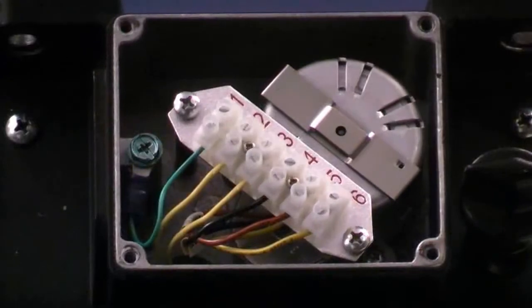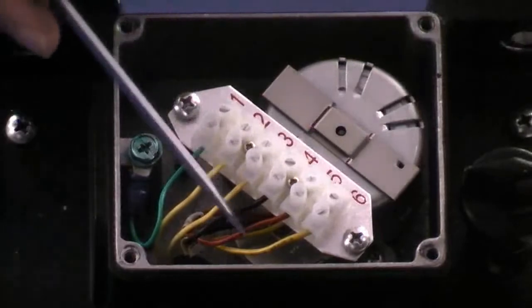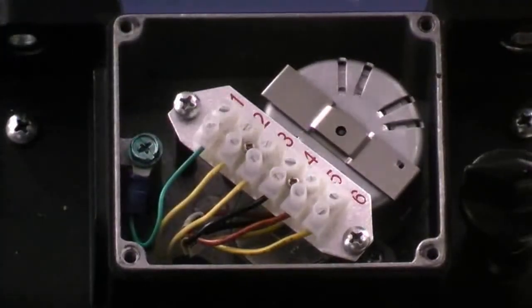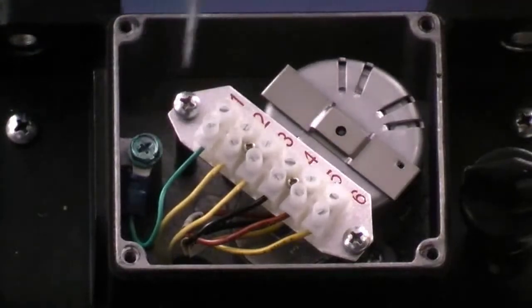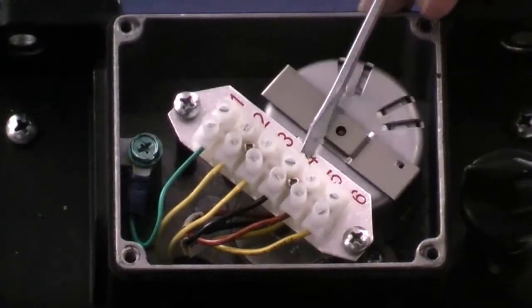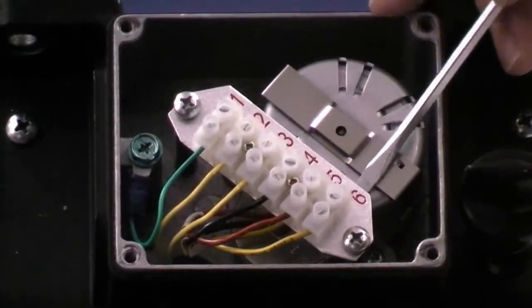Inside the motor gearbox compartment, we have a terminal strip which has already been pre-wired to the motor gearbox. To wire up to this unit, number one is your ground. Two and three are used for the low-level switch. Number four is the 230 volt. Number five is 115 volt. And your number six is your neutral.